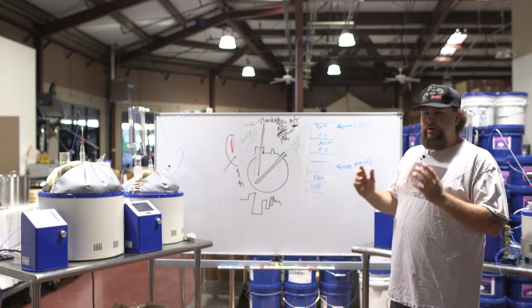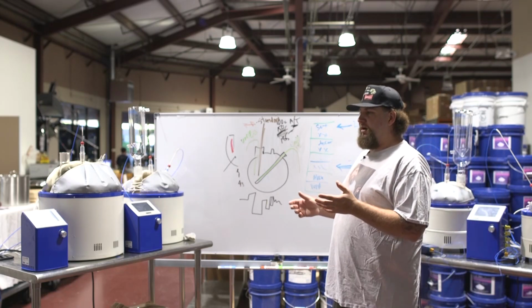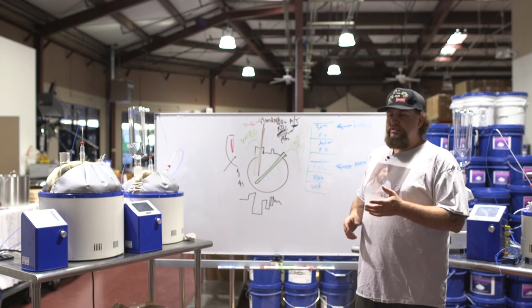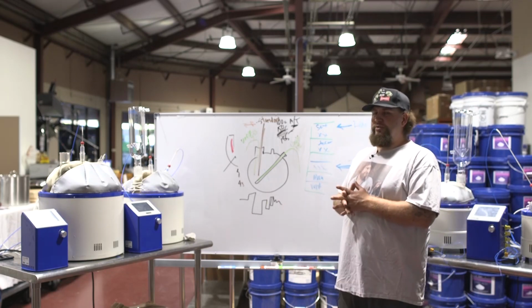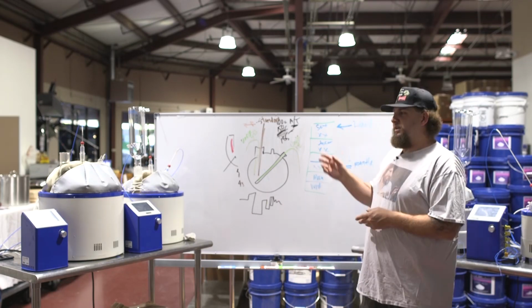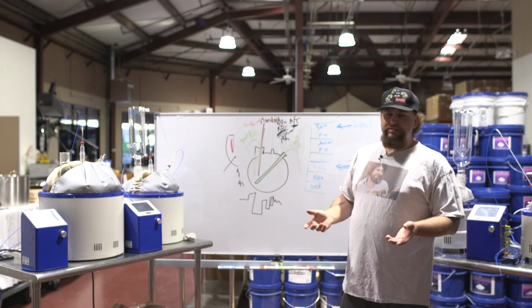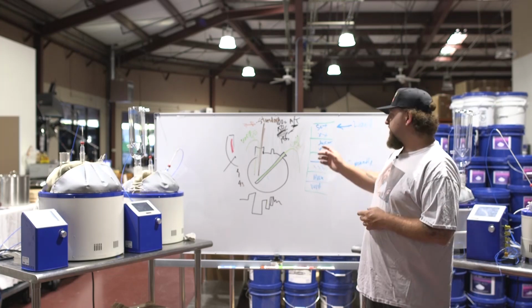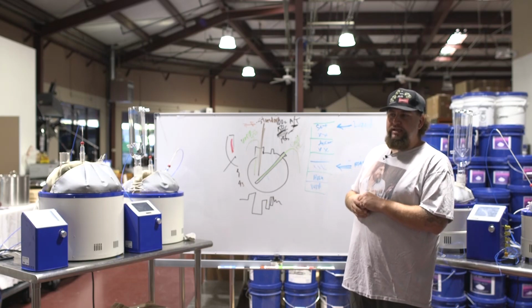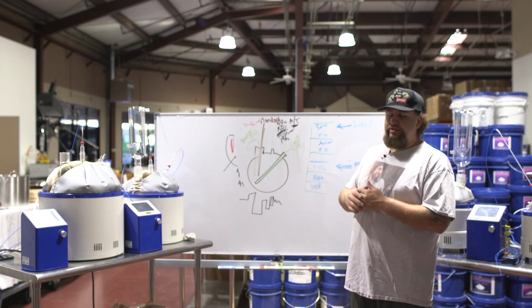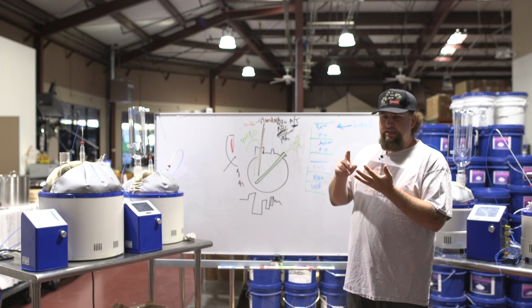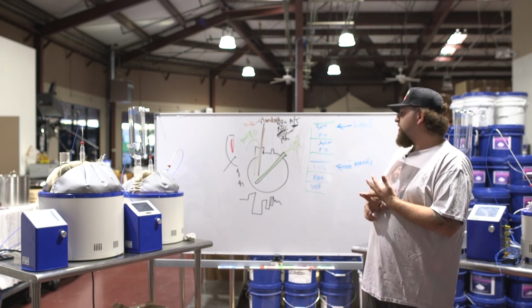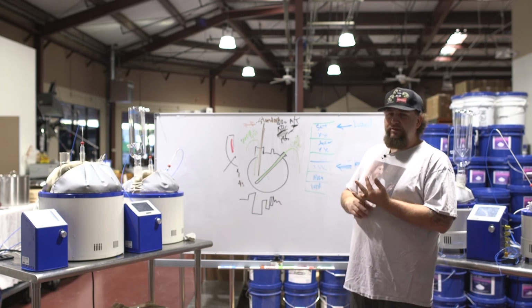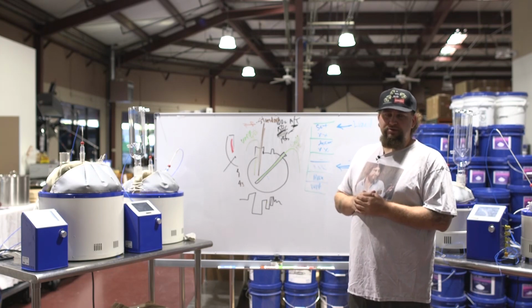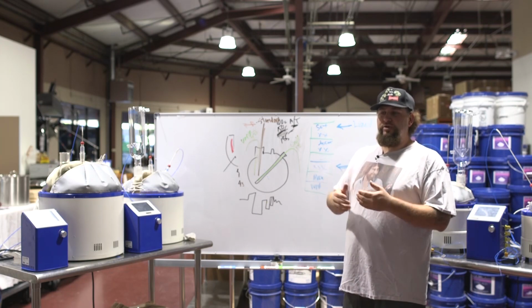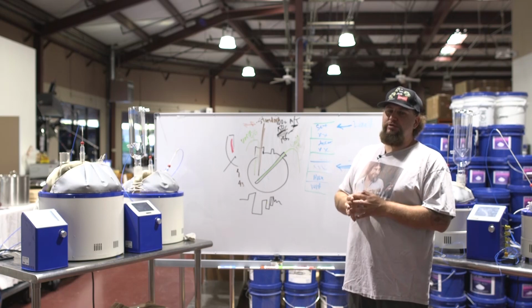The reason is because in both cases, you aren't just signed off once you calibrate that temperature. You have to calibrate the temperature to the process. If you aren't doing it, then the biases won't be set right, and it'll be jumping back and forth. I highly suggest using the liquid bias setting. It's a lot easier. It's really accurate. It uses less wattage, it uses less heat, and it goes up in temperature faster. The other method is mostly for really expensive chemicals or really expensive reactions that can't overshoot or have to be within a certain threshold of a temperature.